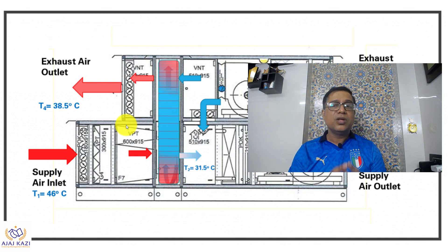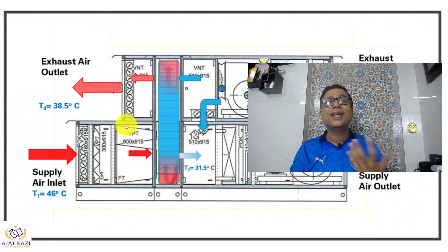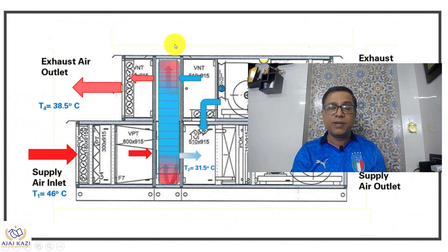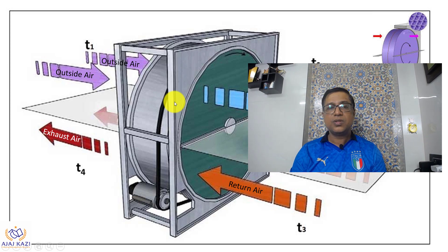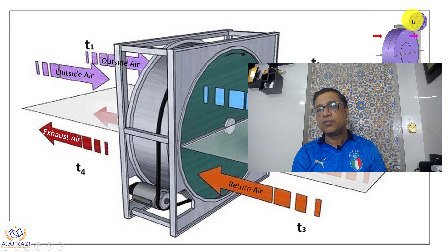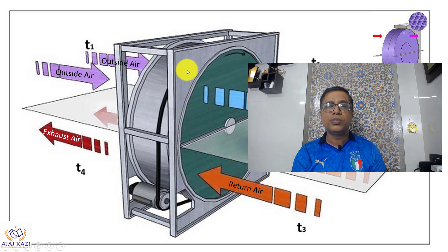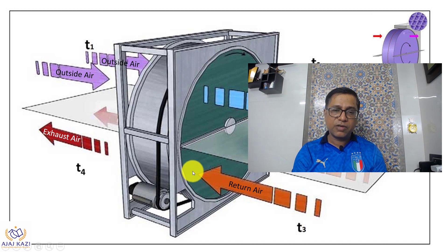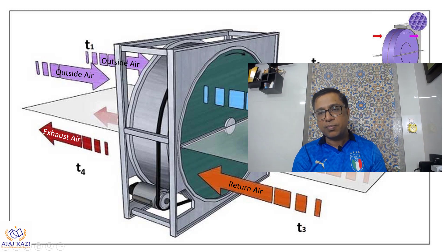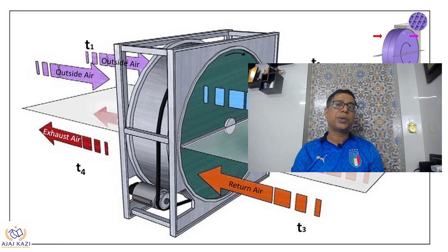This is the fundamental of HRU — heat recovery unit — whose very important part is the heat recovery wheel, which plays an important role. It is generally circular in shape; it is a wheel and it has a motor and rotor. The exhaust air passes over it, the coldness is given to this wheel, and then it gets exhausted. Then the outside fresh air passes over it, and that coldness is transferred to the supply air, which becomes cooler.